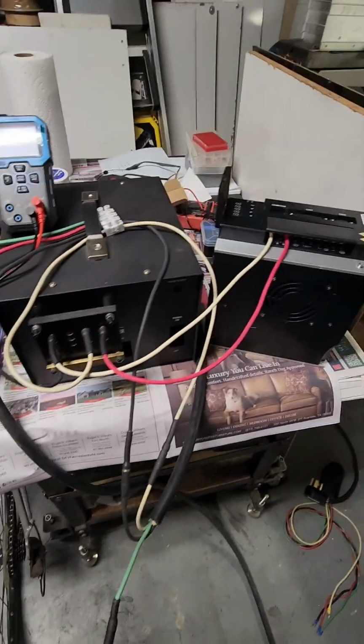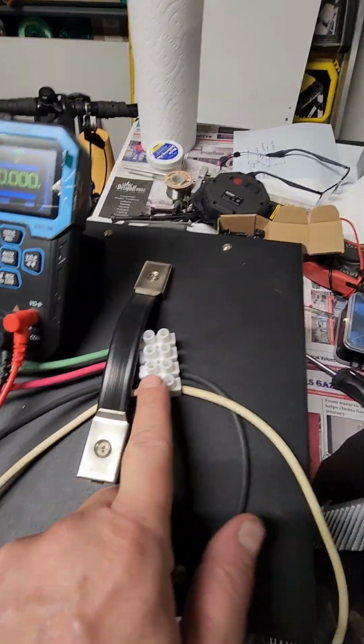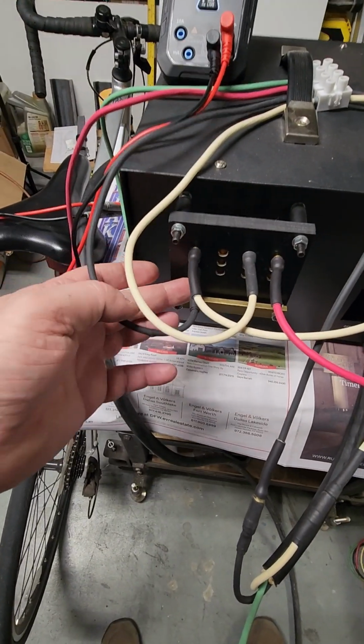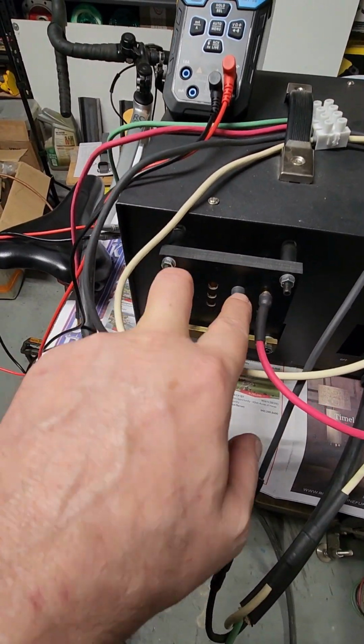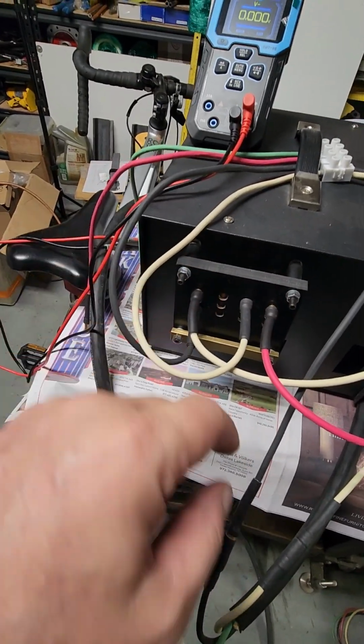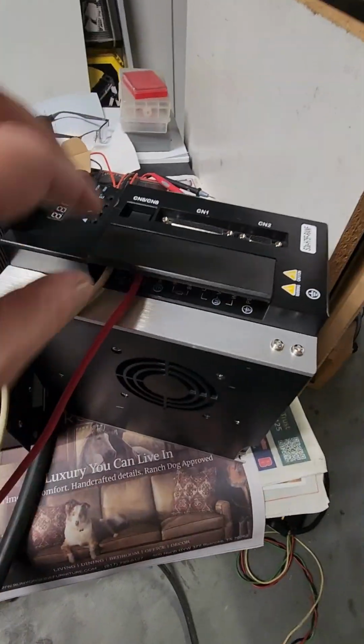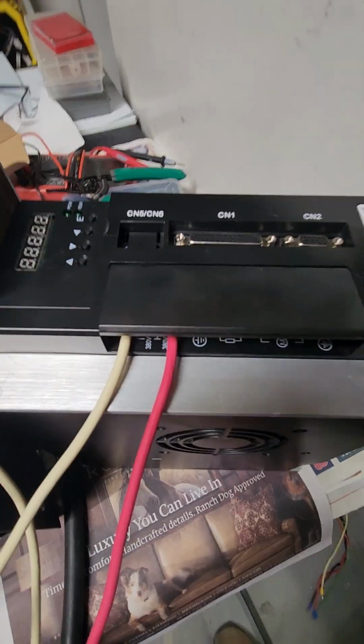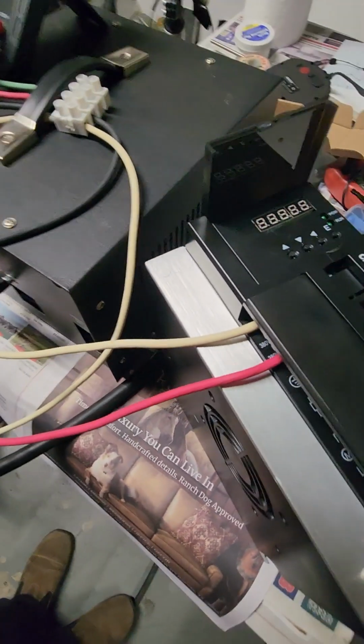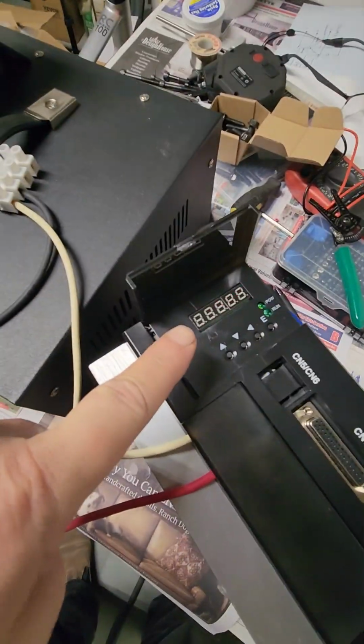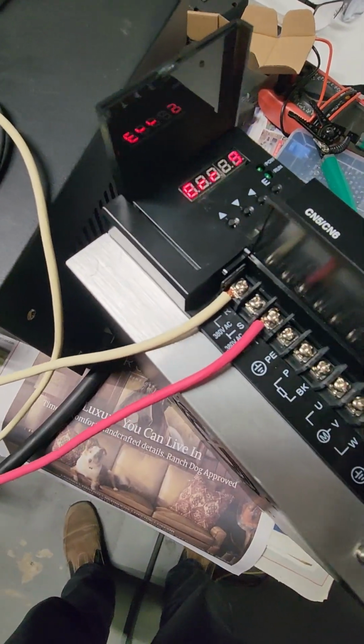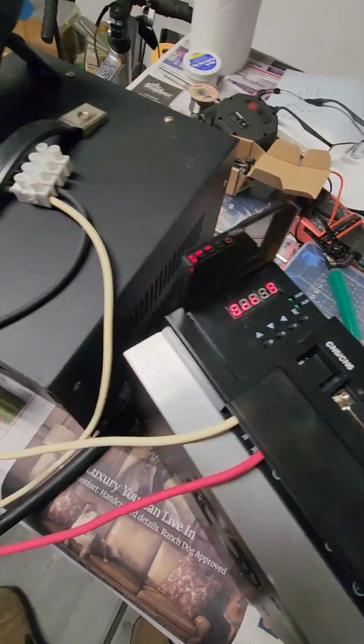Okay, so I have this wired, power comes in here. The two hot wires, it's disconnected now, enters this connector block and then goes here as I mentioned. So one here on this bus and one here, 240 volts, and then from here to here I'm getting 380. So one wire goes to the inverter and the other wire, so these two go into the R and T. So I'm gonna leave this here on the driver. Maybe you can hear that clicking when I'm powering it up. Do you hear that? There's a clicking there, so I think it's fine, it has protection. That error 9 is because the encoder is not connected here, and it's complaining about that. But I think that should be fine.